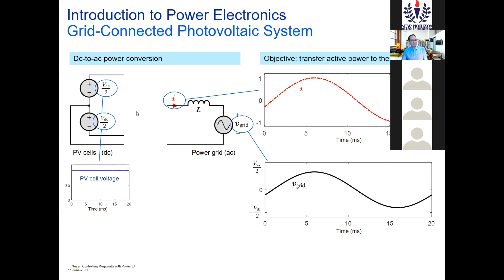In between, we need this inverter. In the simplest case, you could use two switches, an upper switch and a lower switch. These two switches are meant to control, at the terminal of the converter, a desired inverter output voltage, which would drive the current into the grid against the grid voltage. This could be the voltage at your point of common coupling. If you start switching, for example closing the upper switch with the lower one open, then the voltage applied at your converter terminals would be half of the positive DC link voltage.